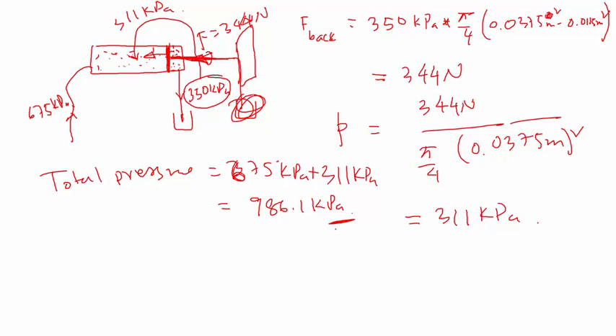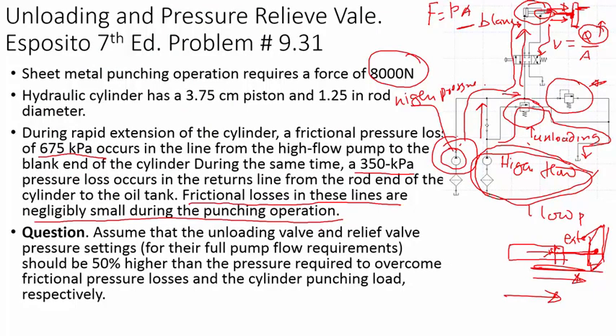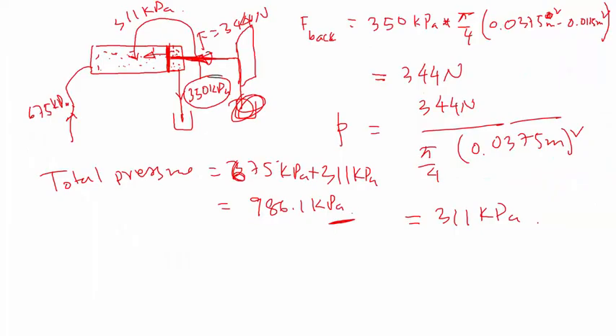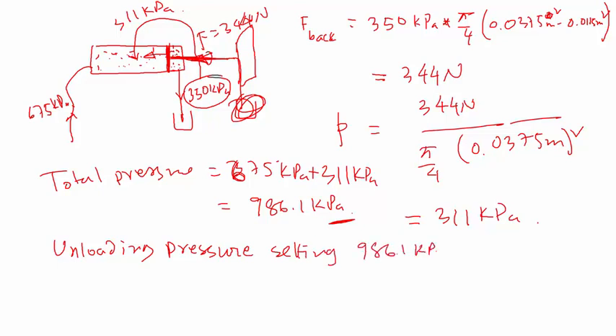To overcome the back pressure and blank-end losses, 986.1 kilopascals would be sufficient. However, to run the operation smoothly, we set the unloading valve pressure 50% higher. Therefore, the unloading valve pressure setting is 986.1 kilopascals times 1.5, which equals 1479 kilopascals.